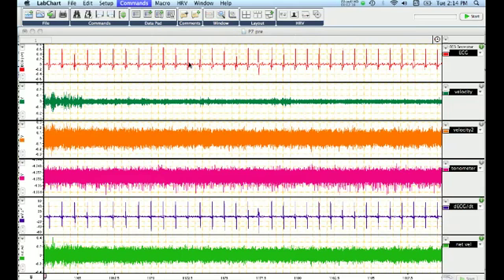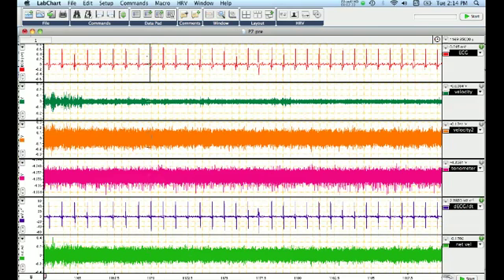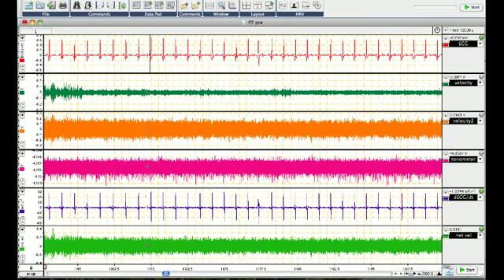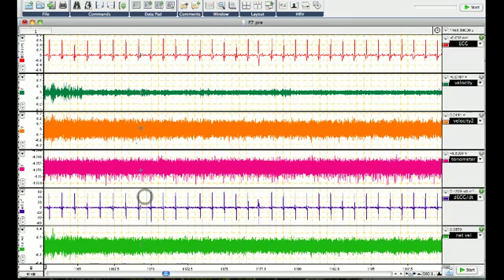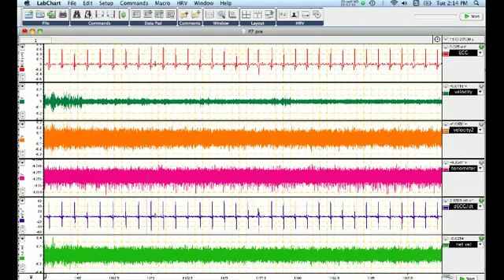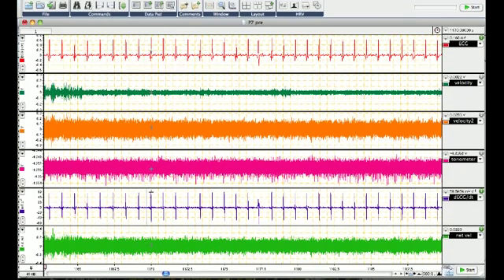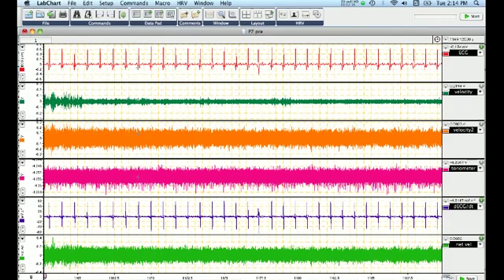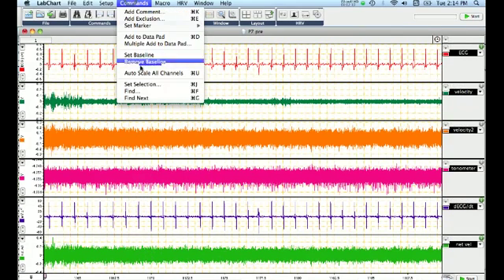In this particular case, it's going and looking through the whole signal, and it says it can't find one. So what I've done is added a derivative channel to the bottom, and instead of using the R spike from this, I'll use the maximum point on the derivative to locate the start of that R interval.